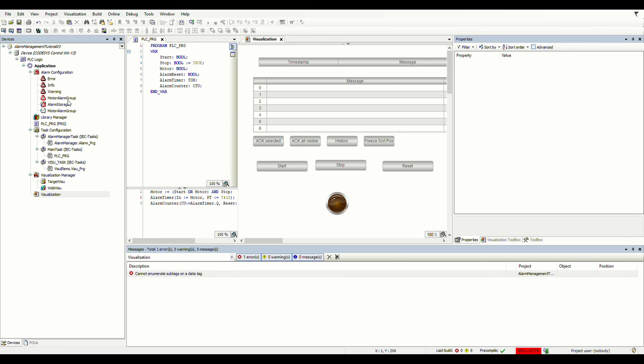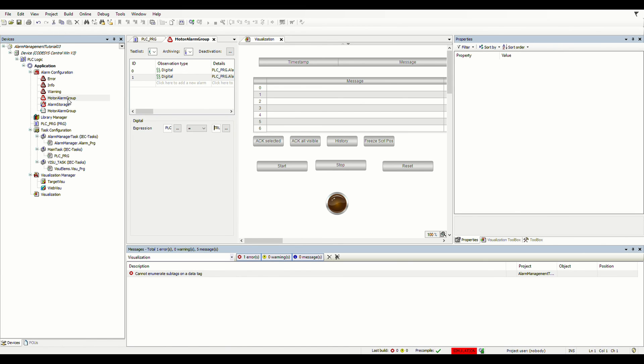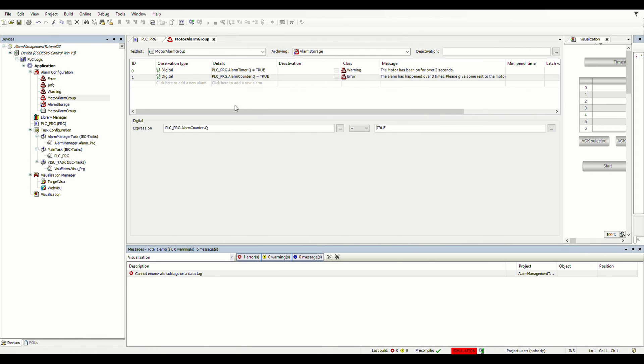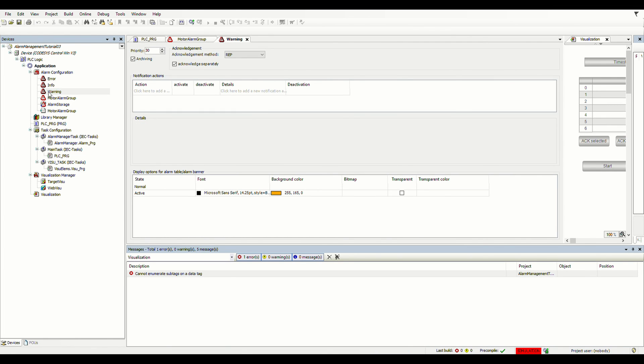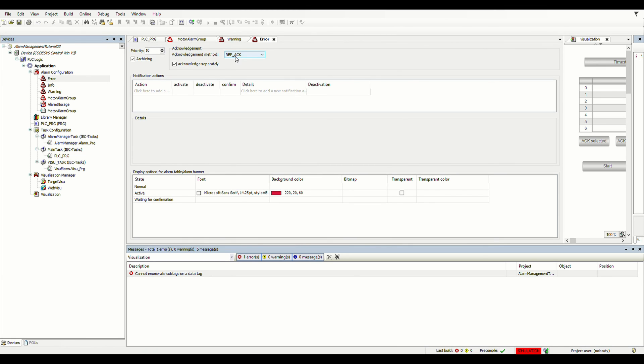Let's look and look at the differences between the two alarm types. For the warning class, the acknowledgement method is set to 'reset' — meaning the alarm disappears automatically when the condition goes away. For the error class, the method is 'reset and acknowledge' — so for this type of alarm, the user must explicitly acknowledge it; otherwise it will remain in the table even after the condition clears.